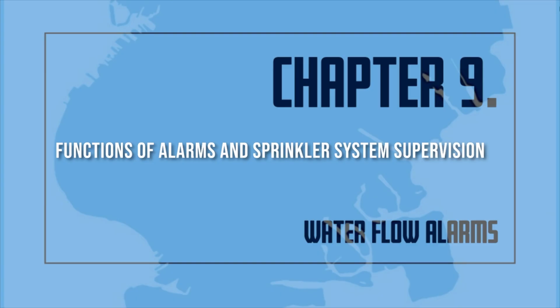It may also send a signal to the central station company. The central station company will then contact the local firehouse. Supervisory devices are often connected to an approved central station company which monitors the sprinkler system for problems with equipment and when sprinkler heads are opened. The central station company should be notified when any control valves are closed for maintenance or repair. This reduces the number of false alarms.